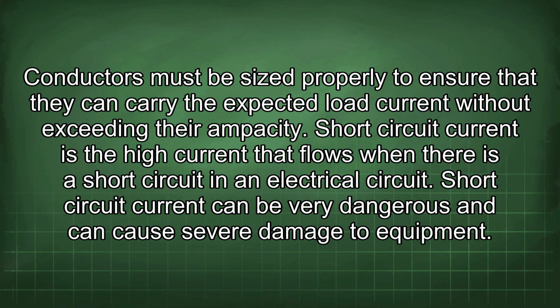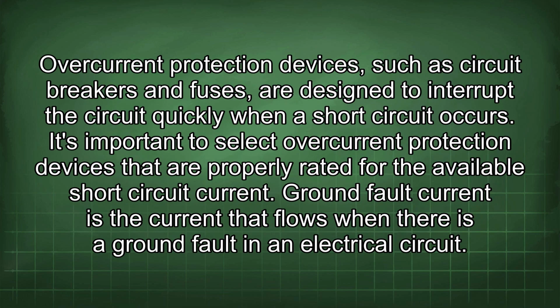Short circuit current is the high current that flows when there is a short circuit in an electrical circuit. Short circuit current can be very dangerous and can cause severe damage to equipment. Overcurrent protection devices, such as circuit breakers and fuses, are designed to interrupt the circuit quickly when a short circuit occurs. It's important to select overcurrent protection devices that are properly rated for the available short circuit current.